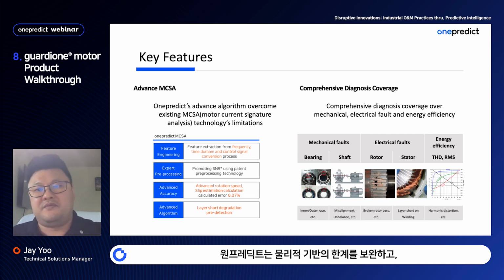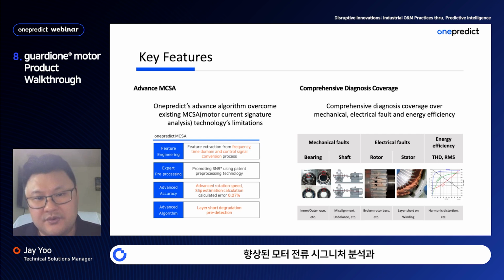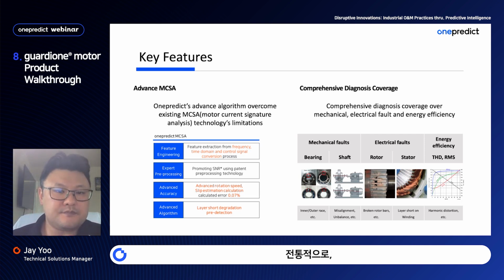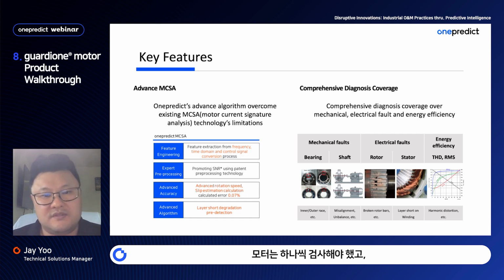ONEPREDICT filled the gap of physics-based limitations with much improved motor current signature analysis, domain knowledge, industrial AI, and a real-time dynamic threshold. Traditionally, you need to inspect motors one by one, and some motors are located deep underground or in hazardous areas so you cannot access them easily. Even worse, to inspect the electrical port, the motor needs to be shut down.